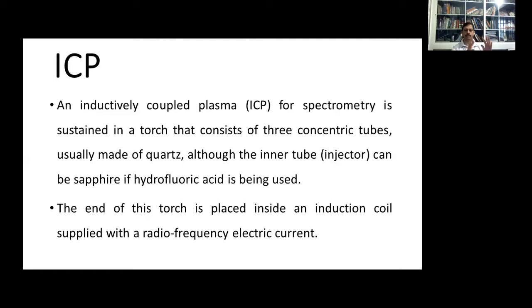So there will be a torch which has 3 concentric tubes, and these tubes are usually made up of quartz. Although the innermost tube, which is called the injector, can be of sapphire. Sapphire may be used to prepare the innermost tube, especially when we use hydrofluoric acid in the experiment. And the outer 2 tubes are almost always made up of quartz. The end of this torch is placed inside an induction coil supplied with radio frequency electric current or RF field.